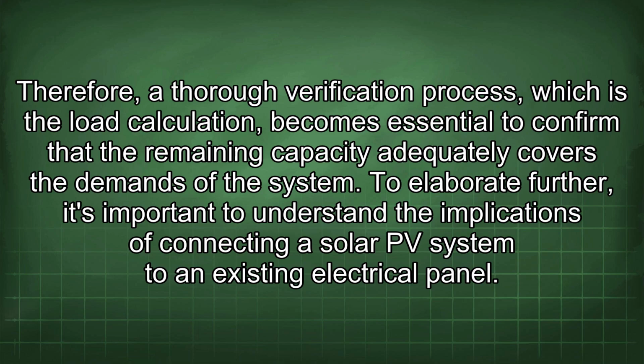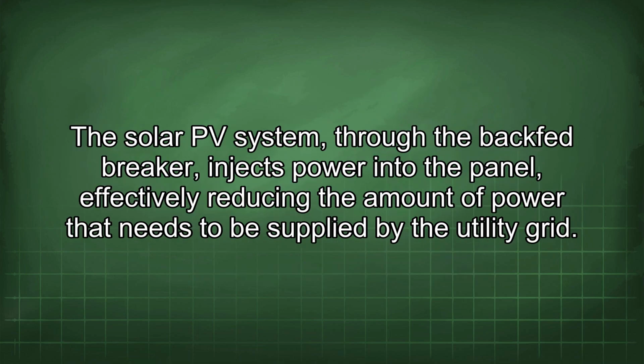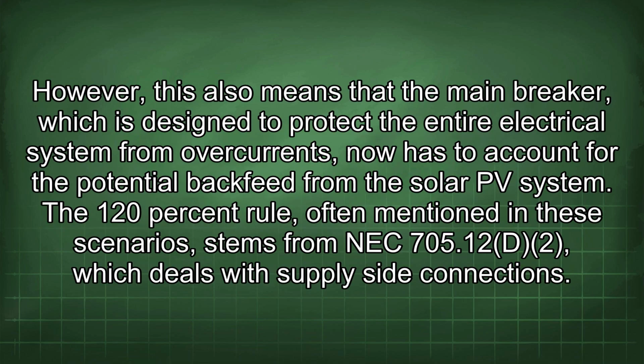To elaborate further, it's important to understand the implications of connecting a solar PV system to an existing electrical panel. The solar PV system, through the backfed breaker, injects power into the panel, effectively reducing the amount of power that needs to be supplied by the utility grid. However, this also means that the main breaker, which is designed to protect the entire electrical system from overcurrents, now has to account for the potential backfeed from the solar PV system.